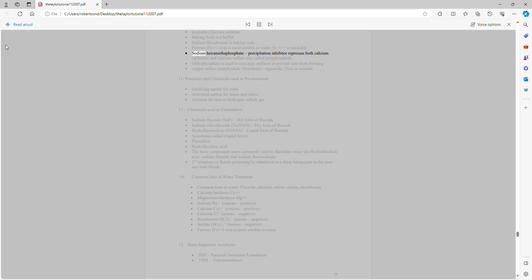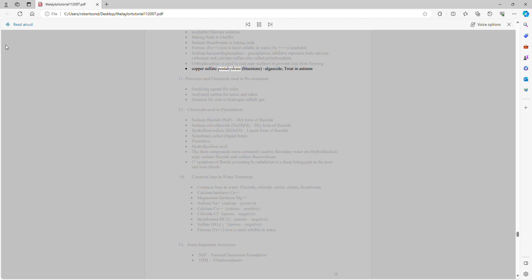Sodium bicarbonate (baking soda) is a buffer. Ferrous (Fe²⁺) iron is most soluble in water. Sodium hexametaphosphate is a precipitation inhibitor that represses both calcium carbonate and calcium sulfate, also called polyphosphate. Orthophosphate is used to coat pipe surfaces to prevent ions from leaching. Copper sulfate pentahydrate (bluestone) is an algaecide; treat in autumn.